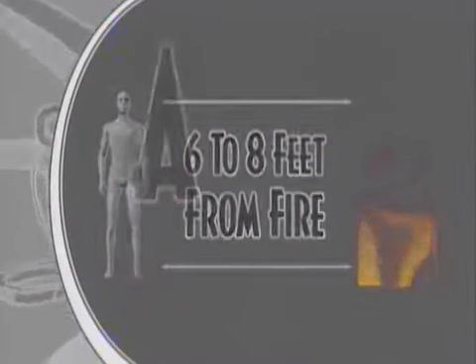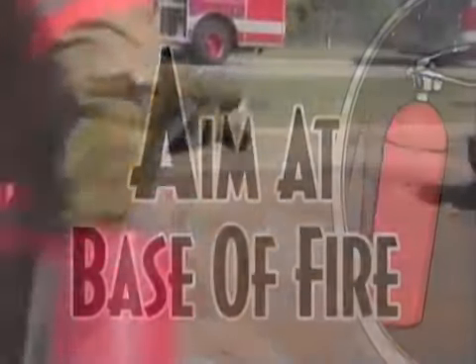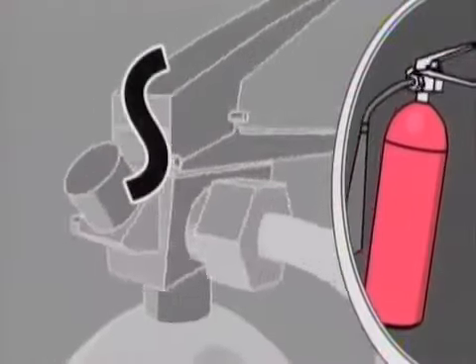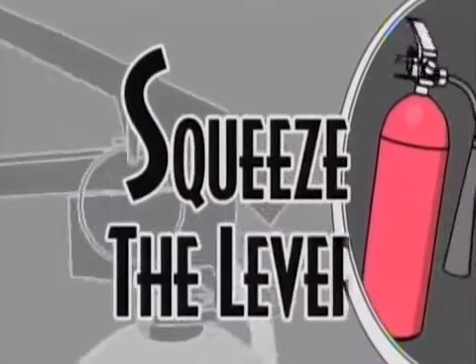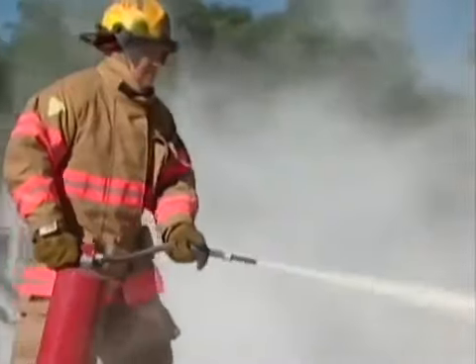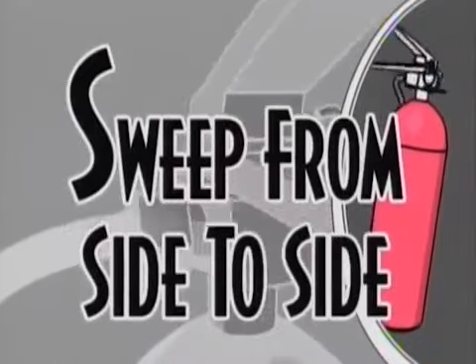Stand 6 to 8 feet away from the fire. A, aim the extinguisher's nozzle or hose low at the base of the fire. S, squeeze the lever that operates the extinguisher. The extinguishing agent will immediately begin to discharge. S, sweep from side to side.